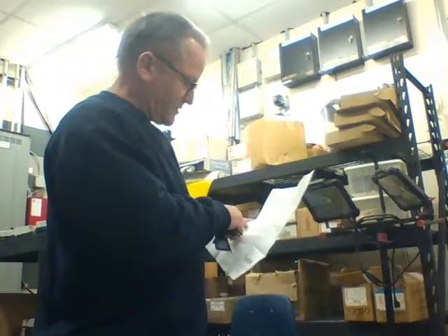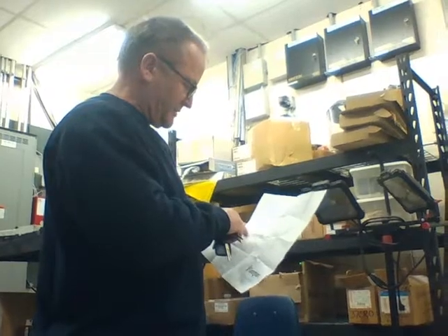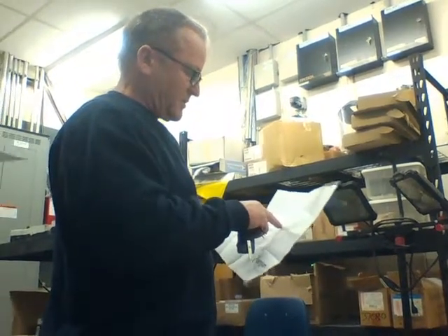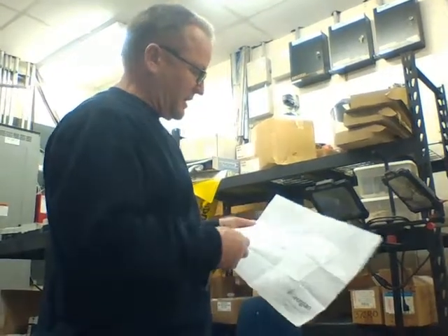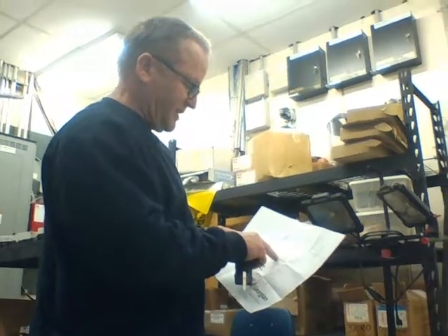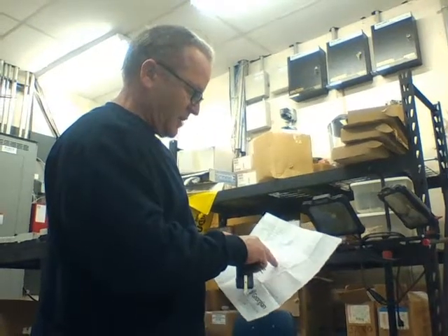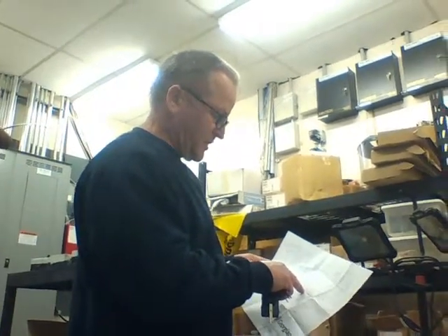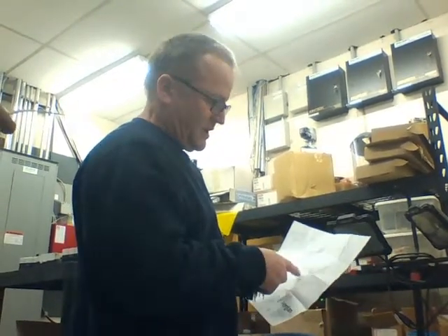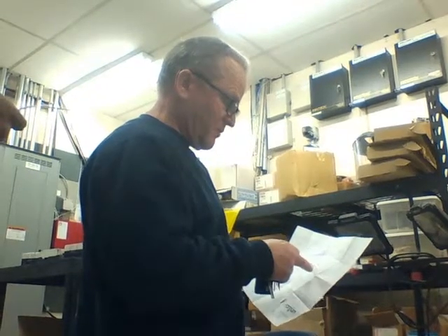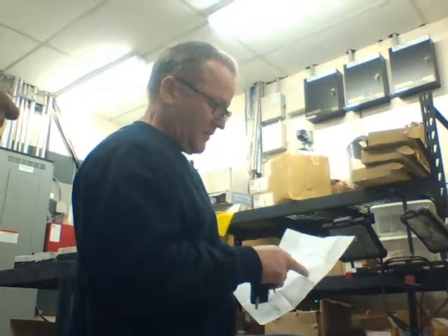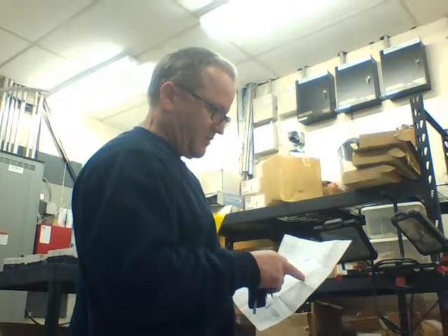It's a 400 amp breaker. The line says basement electrical room 507. It goes to a 600 volt panel in room 507. From there, a 200 amp breaker feeds another 112 kVA transformer, 600 delta to 120/208Y, in room 507, where there's a 100 amp breaker feeding lighting panel D in room 507.